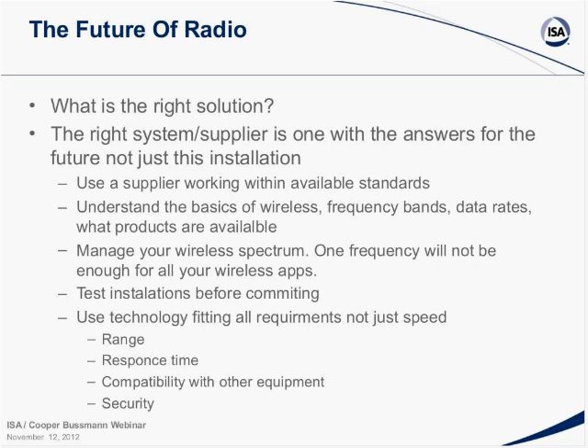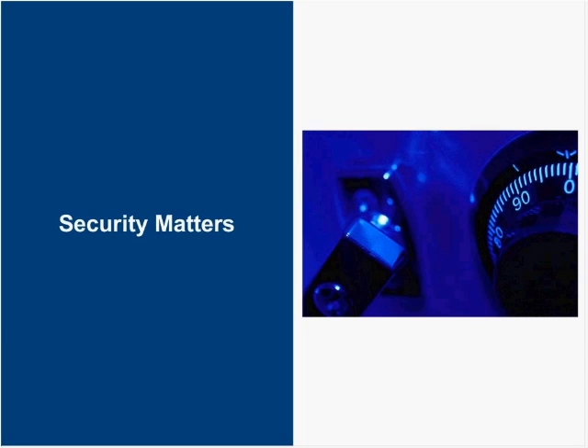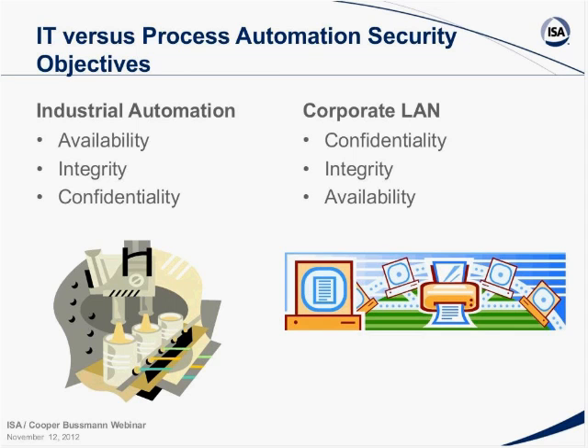And we've talked about security, right? So two different perspectives, like we said, IT and controls here. We're both using the same spectrum. So for industrial automation, the three things we look at are availability, first of all, integrity, and confidentiality. The business LAN or IT people look at confidentiality, integrity, and availability. So corporate people, right, if you get something wrong with your laptop, the first thing they do is isolate you from the network. Well, if we have a problem with a PLC, that's the last thing we want to do, isolate that device from the network, because now we've lost the ability to control that piece of our process, right?